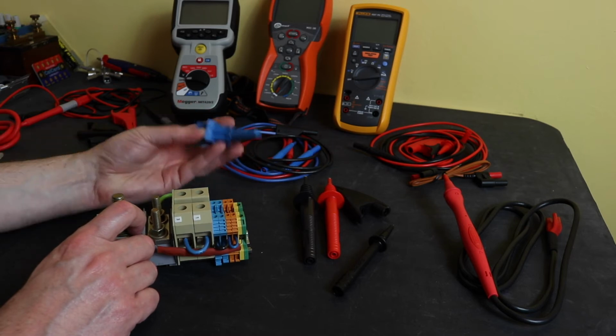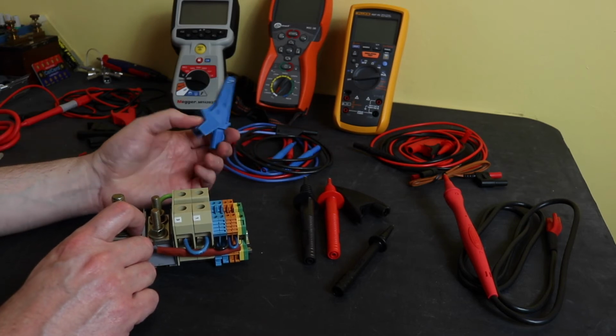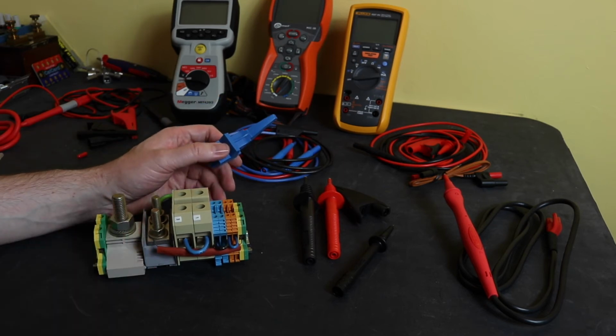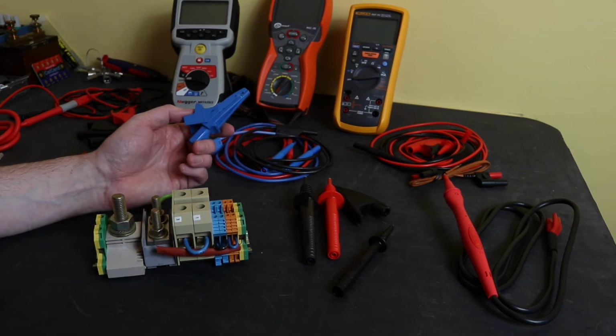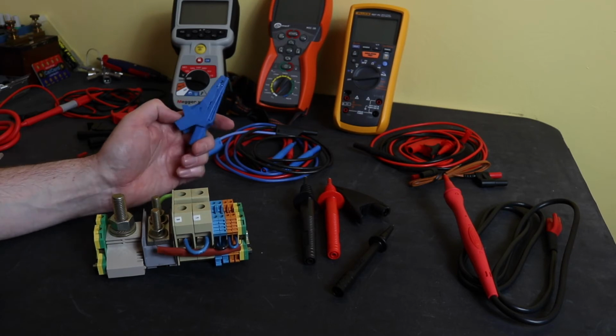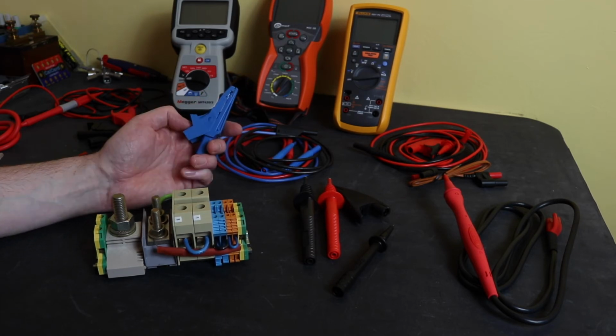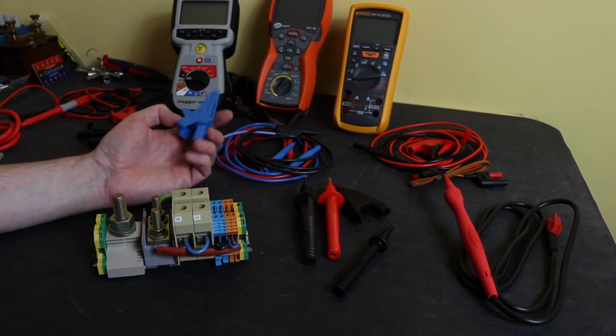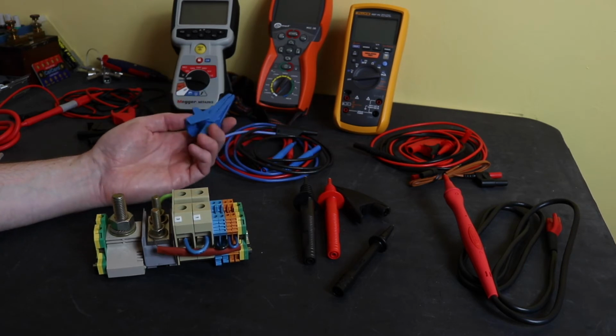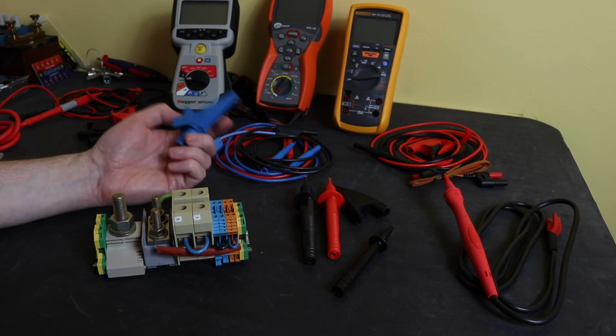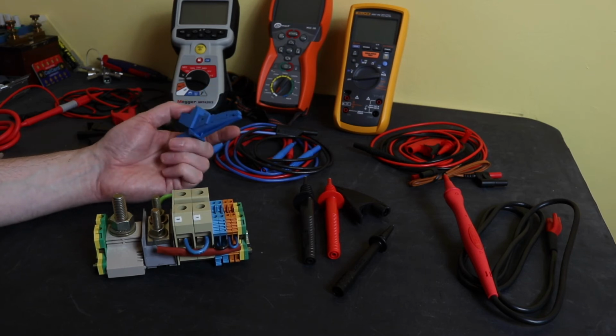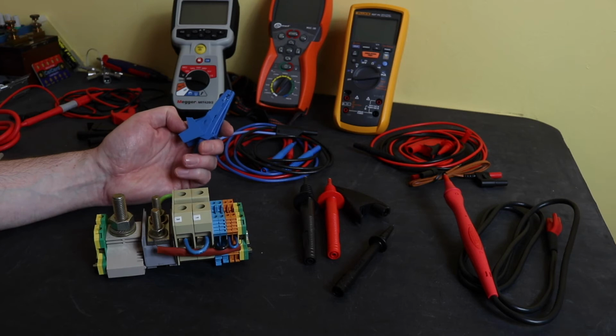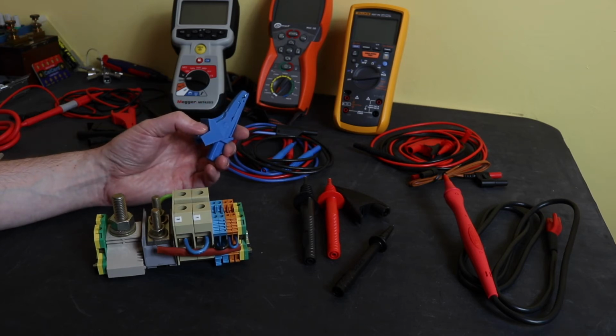Crocodile clip wise, as I said, you only get one crocodile clip with the Sonel. I do not know why. It's an instrument that can carry out DAR and PI testing. Therefore, in my opinion, you would need more than one crocodile clip to do that. You don't want to hold probes on for 10 minutes to carry out an insulation test. That's silly. So I don't know why they don't include it as standard. They will sell you them as optional extras. To my mind, if you're paying £700 for an instrument, it really should come with all the basics that it needs.